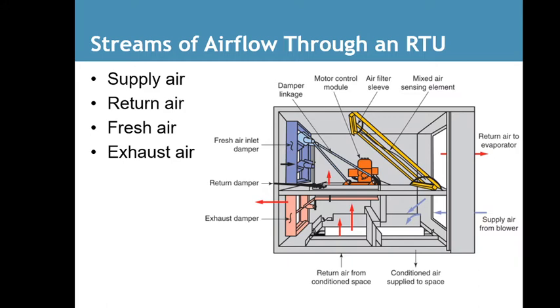Also, they mention on this slide is fresh air and exhaust air. Some units are in buildings that are very tightly sealed, so there's got to be a way to get air inside. If it's not a store where the door is constantly open, and it's more of an office building, the door doesn't have big enough air return to let the smell and the used carbon dioxide get out. So usually they use the fresh air intake and exhaust air. I think this system doesn't show that real well, but we'll go through it a little bit more. The unit we have on the roof does have a fresh air intake. That's that upper blue section, and you can see the lower exhaust system will open up, and these are usually done electronically. They'll open up and exhaust some air sometimes.